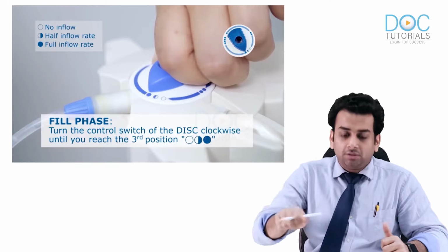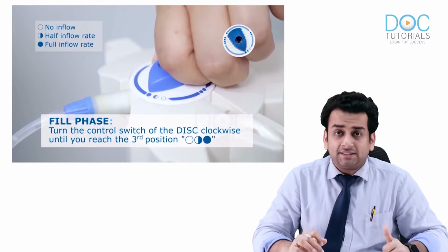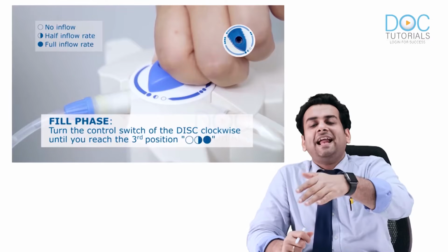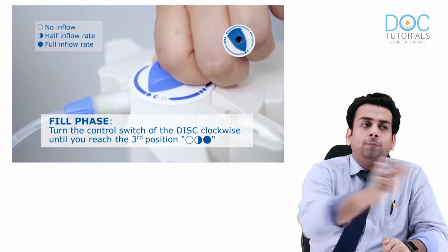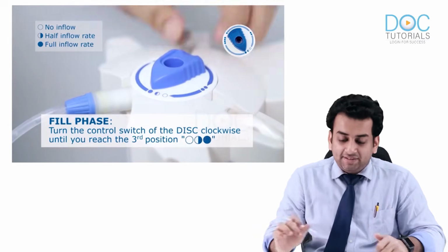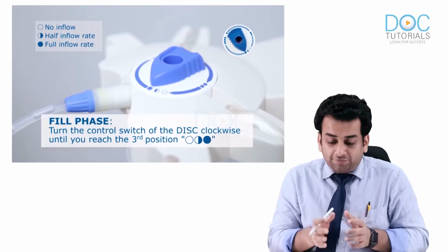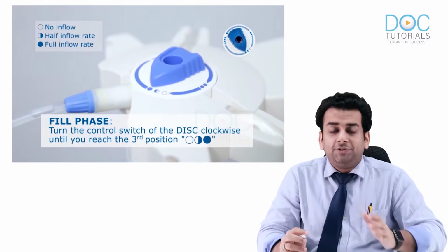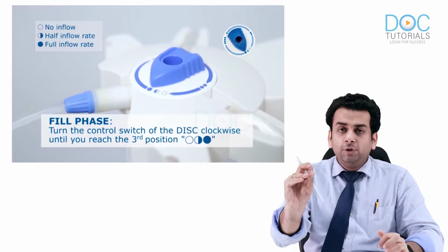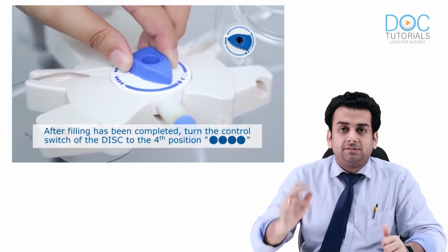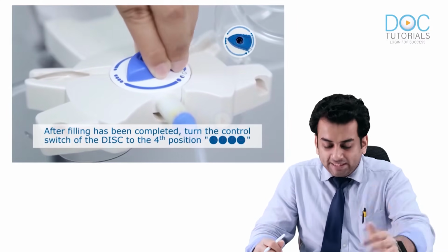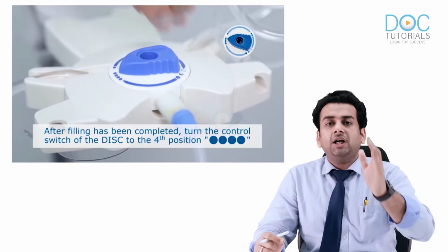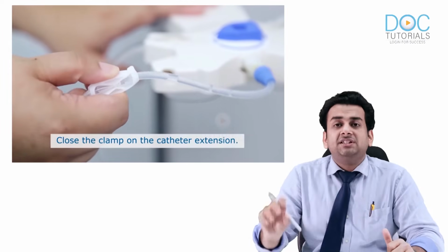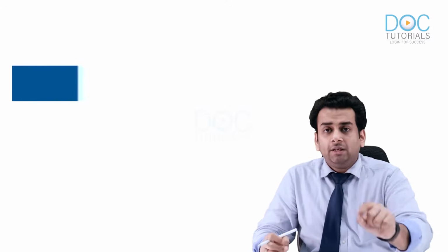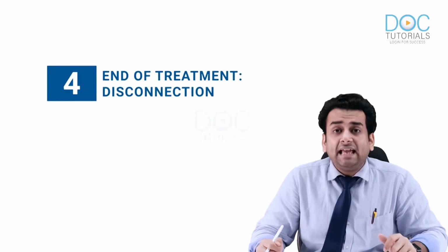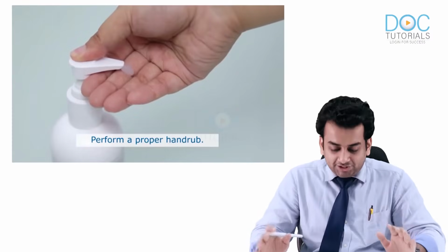The next, if you turn, will be the fill phase. And now it will close the end of the drain bag and the fluid will directly go into the peritoneal cavity, as you can see in this video, which of course can have a half circle phase, which is basically filling at half the pace, and a full circle, which is filling at full pace. After the filling has been completed, you turn it again to the last, which is the disconnect portion. Then you close the clamp and then you will do the disconnection.